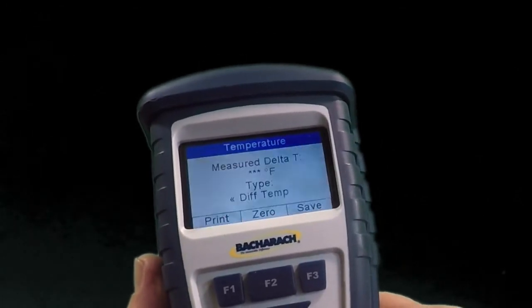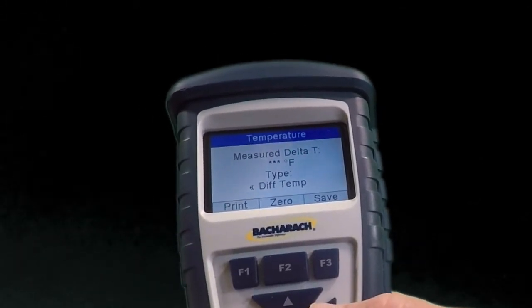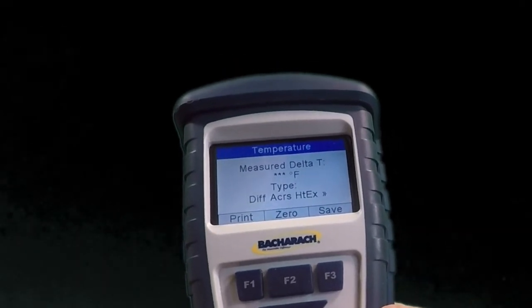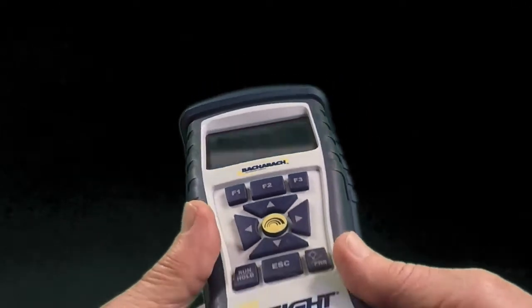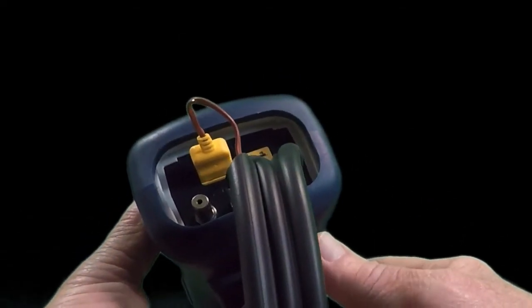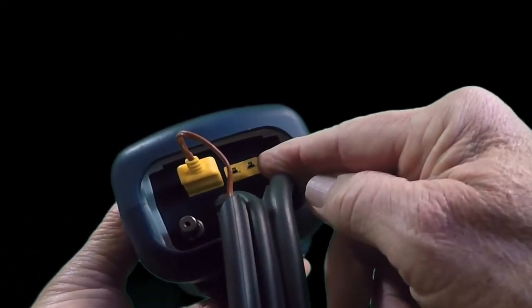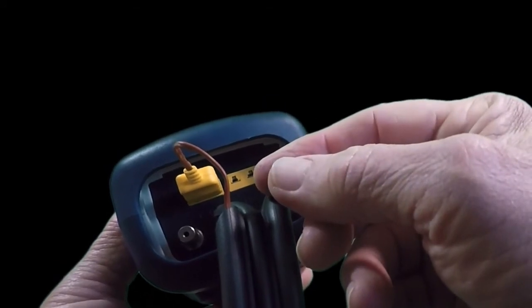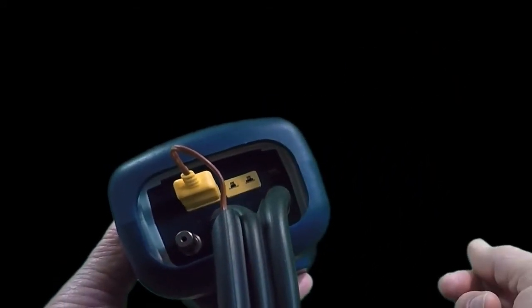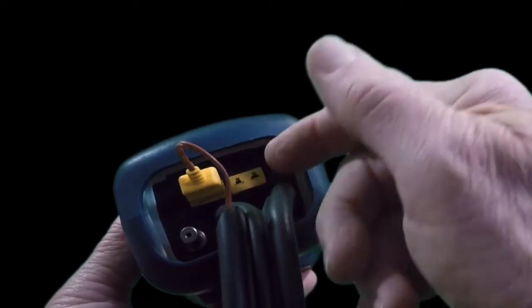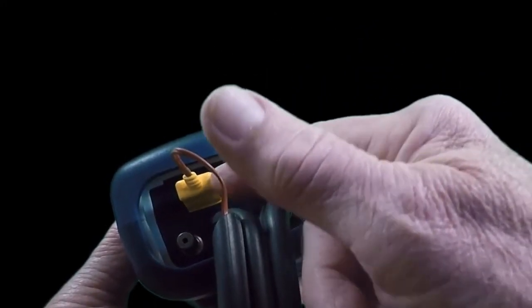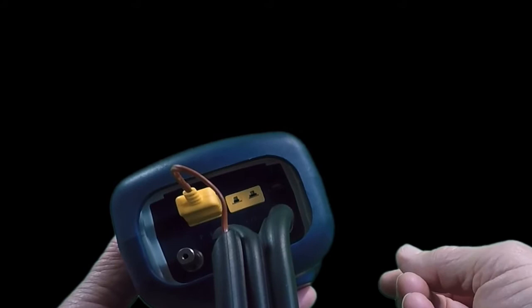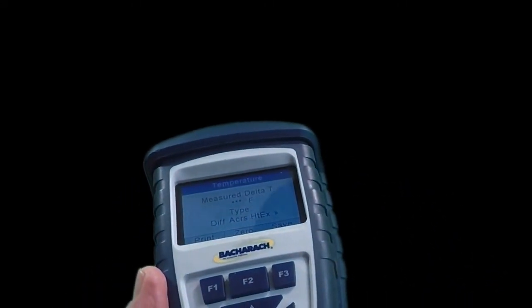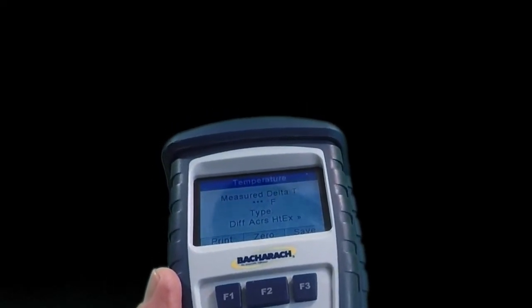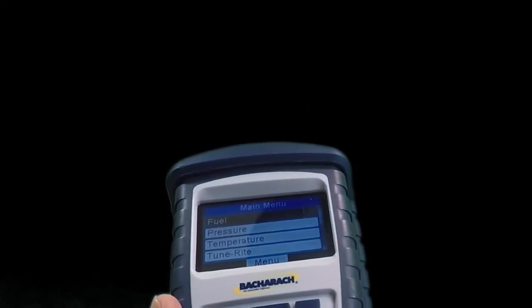Temperature, again, same kind of thing. You can do differential temperature, you can do temperature across the heat exchanger, whatever. And what you'll also need to do to get those readings is to get an auxiliary thermocouple, any K-type thermocouple. That's a standard of the industry. Any K-type thermocouple will fit in there. You can use that as one of them, and you can use the probe as the other, or if you have two just generic K-type thermocouples, that will give you that temperature rise or temperature drop, whatever piece of information you're looking for. Okay, then to get back to the menu, we'll hit enter.